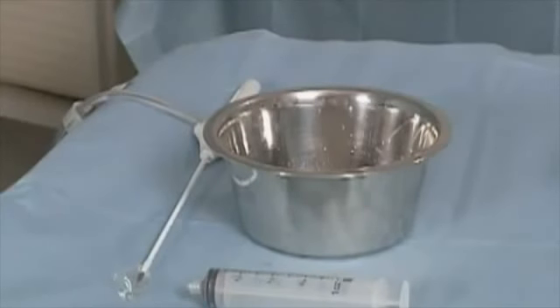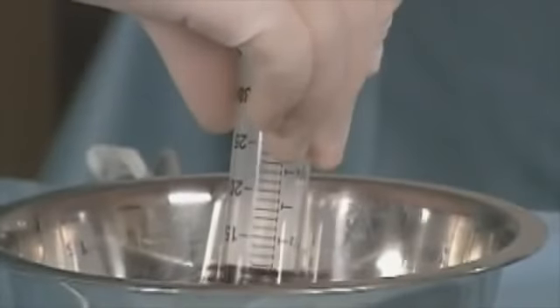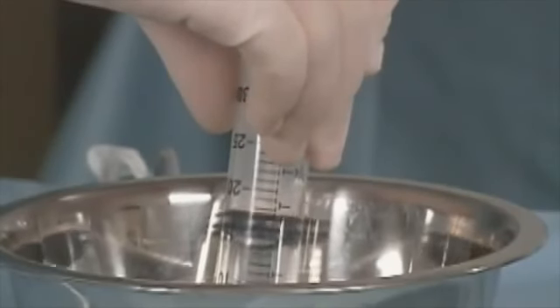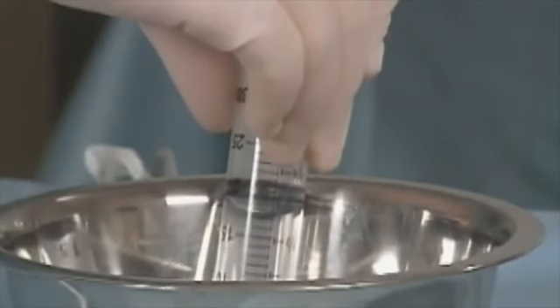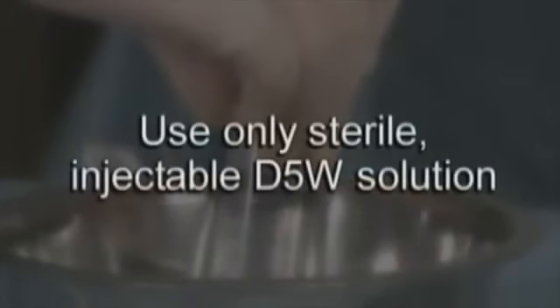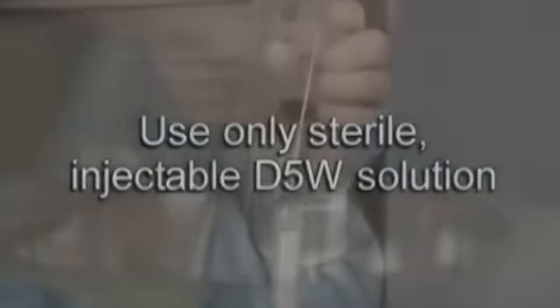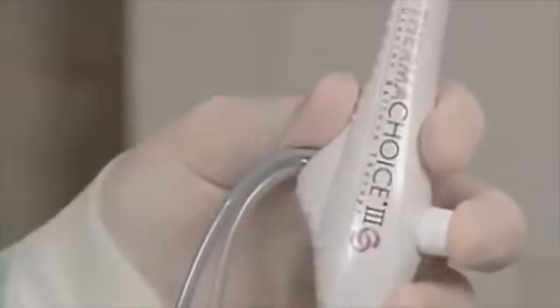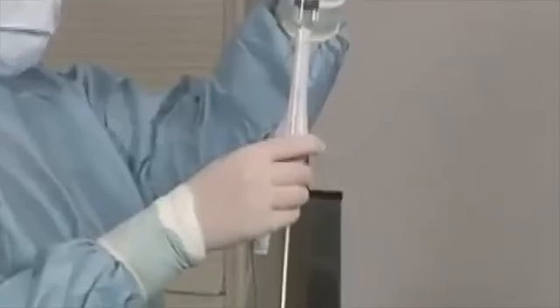Priming evacuates the air and creates a low-profile balloon for insertion into the uterus. To prime the catheter, first fill the syringe slowly with up to 20 cc's of D5W. Use only sterile injectable D5W solution. Use of other fluids may compromise the catheter. Then firmly attach the syringe to the catheter. Hold the catheter, pointing it down to the floor, and depress the trumpet valve, filling the balloon with up to 20 cc's of fluid.